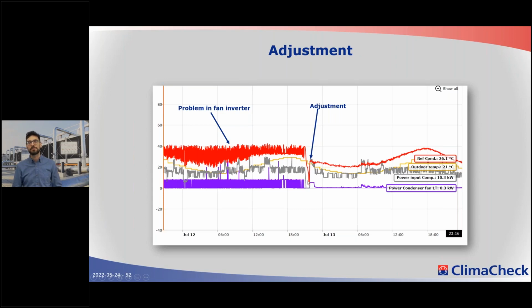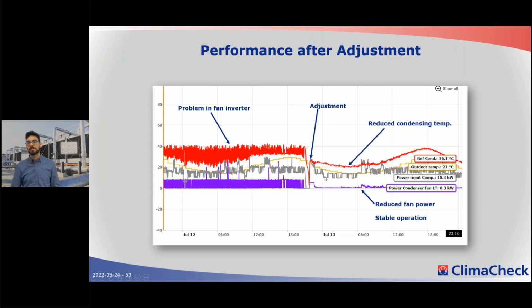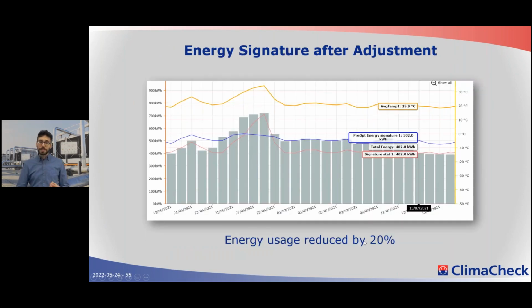Now, this is taking a few minutes. We know exactly what the problem was. The contractor doesn't need to waste time by going there and checking everything again. We know exactly what needs to be fixed, and it has been fixed in a matter of a few minutes. And the results: we've got reduced condensing temperature, a much more stable system, and we're talking about 20% energy reduction. So if we didn't do this change, this system would use 500 kilowatt hours during the day. But because we've made this simple change, now it's using 400 kilowatt hours during the day.